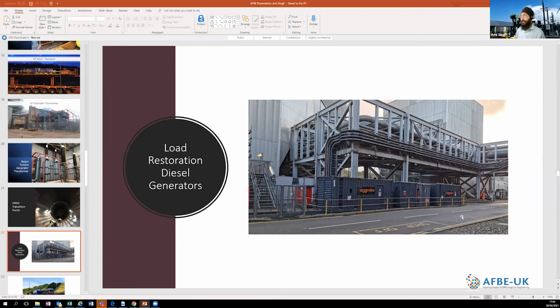These generators you see on my screen are only for load restoration, meaning if the supply from National Grid were to go down and the grid goes black, when power is restored to Peterhead Power Station we have critical supplies, lube oil systems, the generators are not degassed, etc. There's a whole list of critical services that ensure supply is maintained at all times, so once National Grid restores supply we can promptly come back online. We currently have a contract with National Grid for load restoration. I don't feel comfortable giving the exact number of hours, but as soon as supply is restored we have to come back online within a certain number of hours.